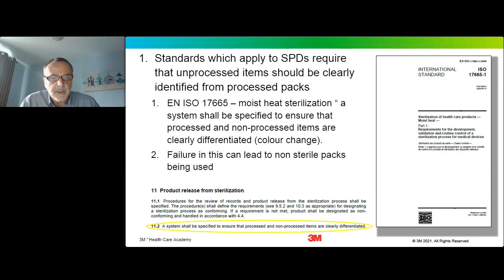You might also have track and trace systems, so some kind of electronic means of identifying which batches have been put through the sterilization process. But of course, in the hospital SPD, the easiest and most obvious way of differentiating processed and non-processed items is through the use of an indicator tape, or also labels, and rigid container locks are also available that will contain a process indicator. Now, failure to use this kind of approach can lead to non-sterile packs being used. And that, of course, is the last thing we want to happen, because it puts patients at risk of getting infections or worse.